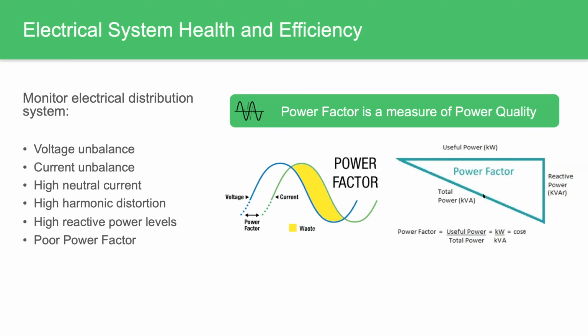So things like voltage and current imbalance are useful for detecting things like single-phase faults throughout the system, or problems within a piece of equipment that's no longer drawing three-phase power evenly. Things to look for are higher than normal neutral current levels, which can identify grounding problems in the system or inside equipment. You can also look at total harmonic distortion. Harmonics are caused by nonlinear loads, things like computers, PLCs, and variable speed drives. Really any equipment with switch mode power supplies creates current harmonics that contribute to voltage distortion.